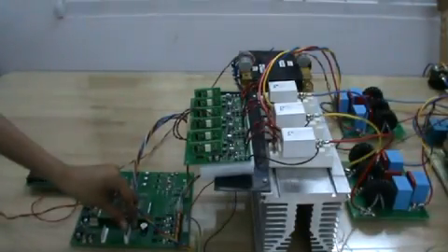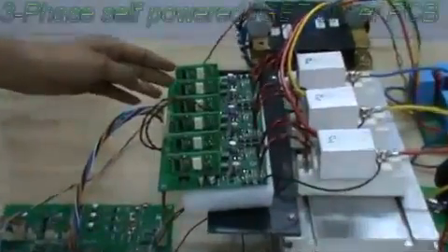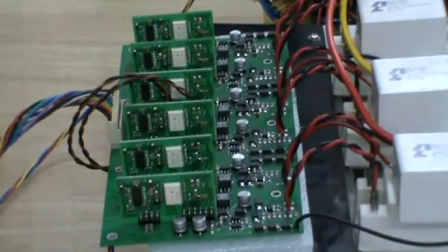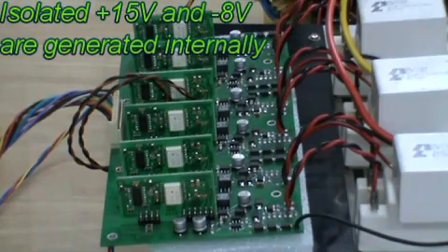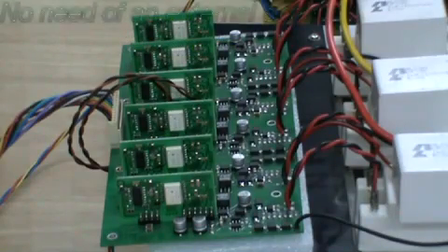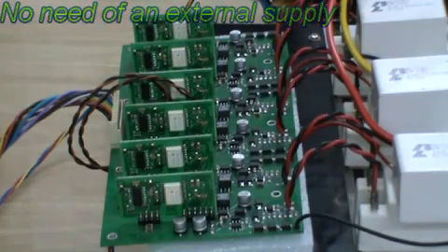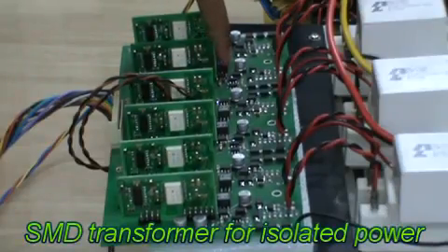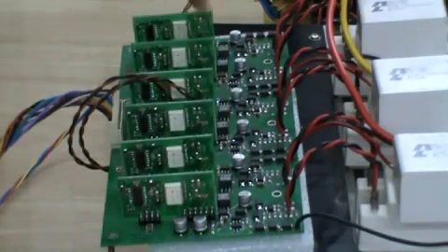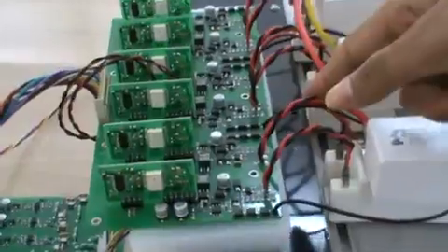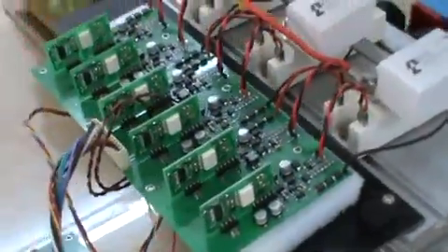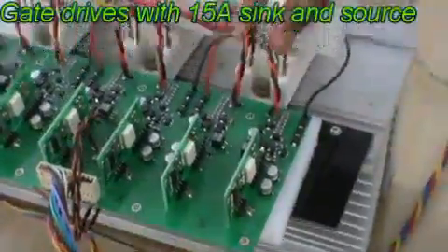The PWM drive from the DSP is connected to 3-phase self-powered IGBT driver PCB. In this 3-phase self-powered IGBT driver, the isolated power supplies plus 15 volt and minus 8 volt to all the IGBTs are generated internally. There is no need to provide an external isolated power supply. These are the SMD transformers used for isolated power supply. These are the gate drives connected to the gate and emitter of each IGBT module. Each gate drive has a peak current of 15 ampere sink or source.